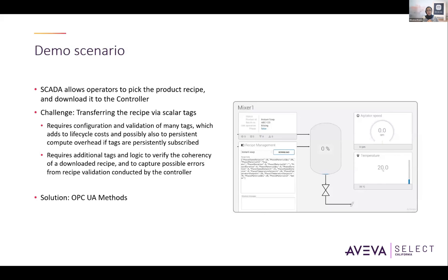Additionally, breaking the recipe into many tags causes a loss of coherency — a loss that may require extra application logic to mitigate. If the controller is able to validate recipes, there may still be a need to configure and validate additional tags to pass and capture the validation results from the controller to SCADA. OPC UA methods can help by maintaining the integrity of the recipe and passing it to the controller as a single atomic transaction — sending the whole recipe to the controller using this method and returning the result of recipe validation by the controller.